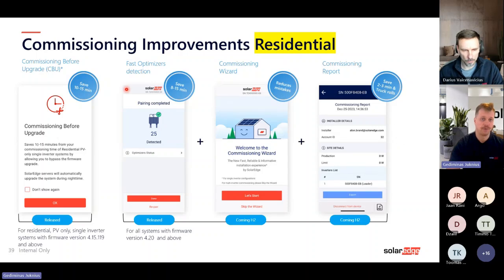The second thing we improved is the optimizer detection. It used to take approximately 5 minutes or maybe more, depending on the site size, to do the pairing. Now you set how many optimizers you actually installed. That means the inverter knows how many optimizers it needs to look for, and the process goes much faster. For newcomers, for those who are not installing SolarEdge quite often, or who never installed SolarEdge with a battery, we made a commissioning wizard. Basically, it's a step-by-step process. Once you've connected the modules to the inverter, you can just click start, next, next, and the app will tell you what to do and what to check step by step, so you will not miss anything.